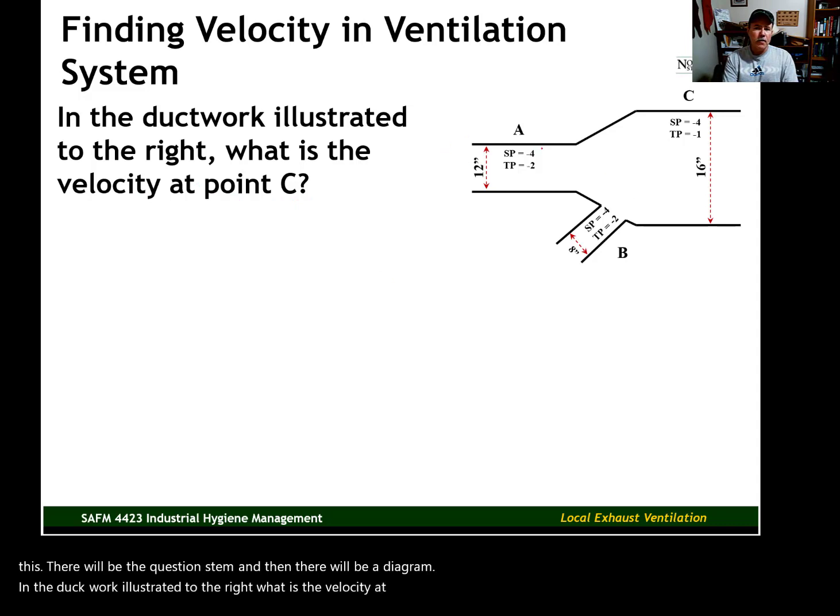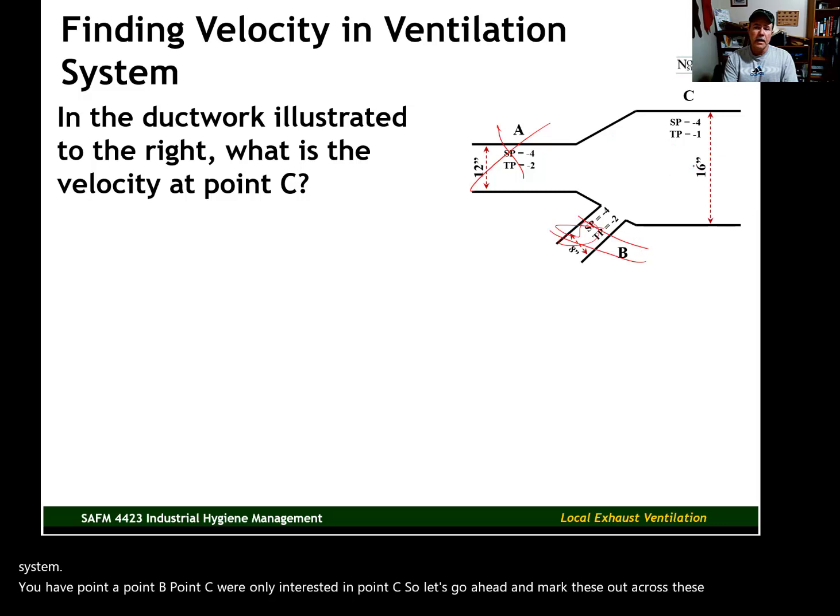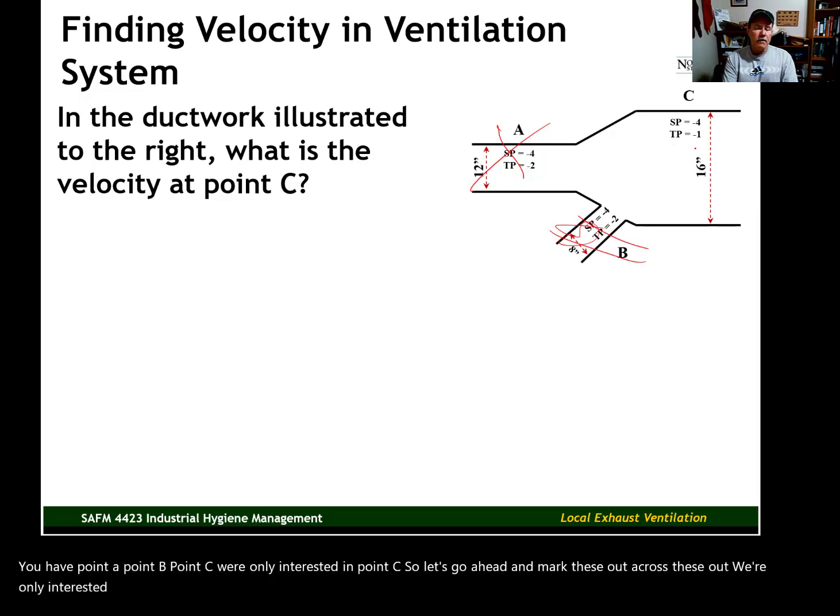You have three different points within this ductwork system. You have point A, point B, point C. We're only interested in point C, so let's go ahead and mark these out. Cross these out. We're only interested in what the velocity is in this 16-inch ductwork with a static pressure of minus 4 and a total pressure of minus 1.